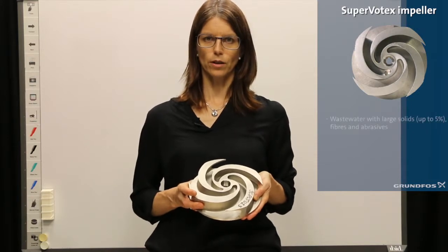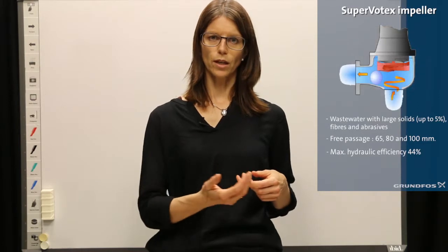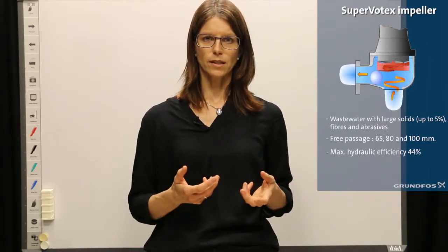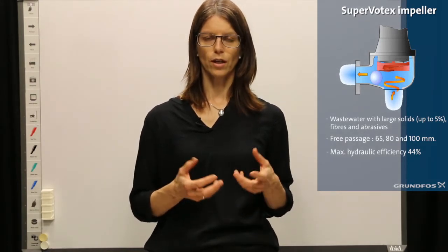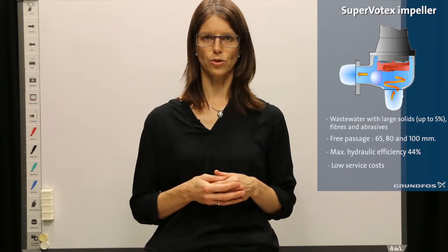Here you see the super vortex impeller offered by Grundfos. This impeller is suitable for wastewater with large solids, fibers and abrasives. It is available with a free passage of 65, 80 and 100 millimeters. The efficiency is quite low compared to the tube impeller — a maximum of 44 percent. However, the non-clogging capabilities are better because the flow of wastewater passes outside the impeller. This means the risk for clogging is low, service visits are reduced, and therefore service costs can be reduced with this impeller.